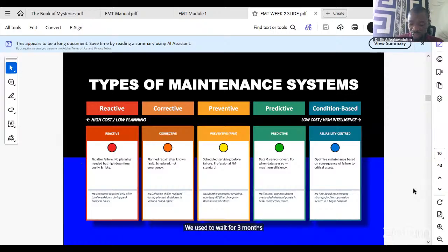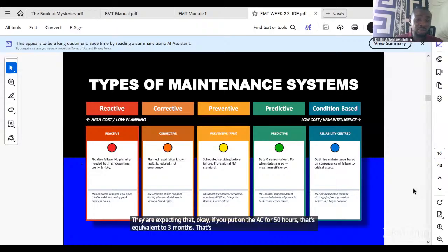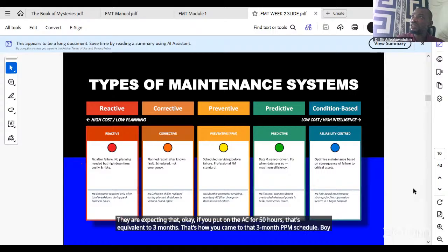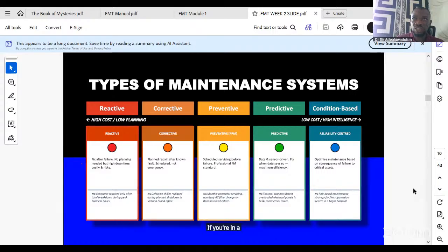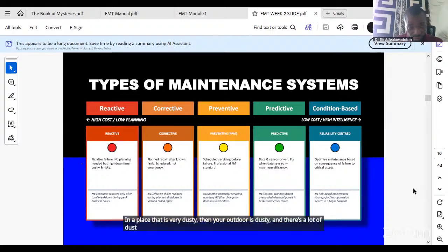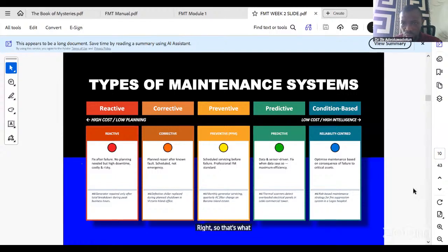That's what predictive maintenance does. For example, if running the AC for 50 hours is equivalent to 3 months, that's how we arrived at that 3-month PPM schedule. But if you're in a very dusty place, with a lot of dust outdoors, you might not have to wait for 3 months. That's what predictive maintenance would do for you.